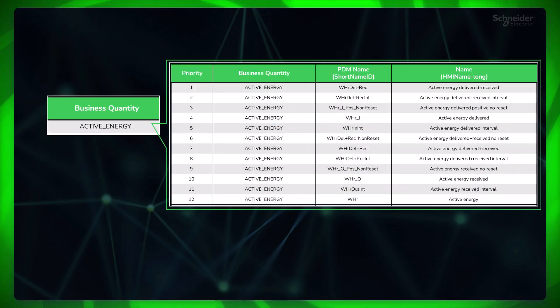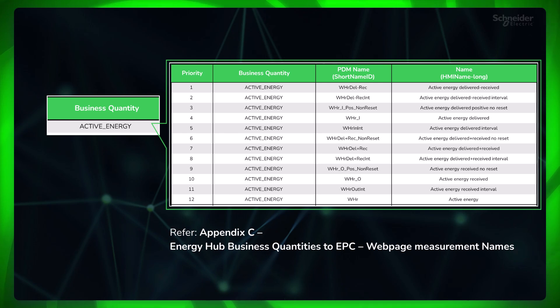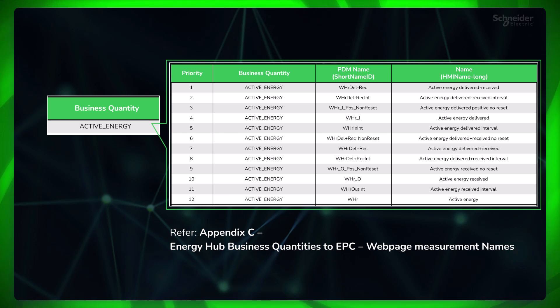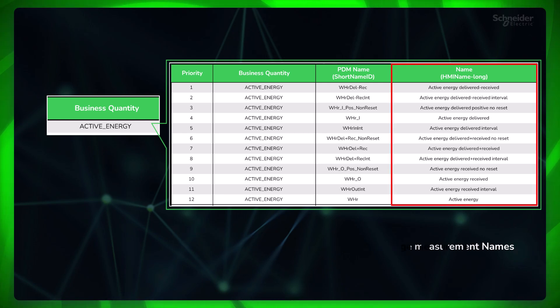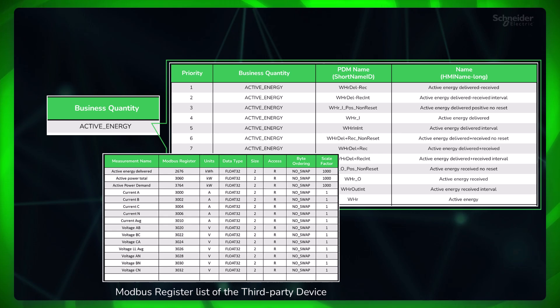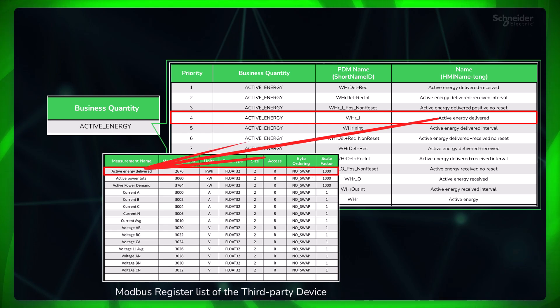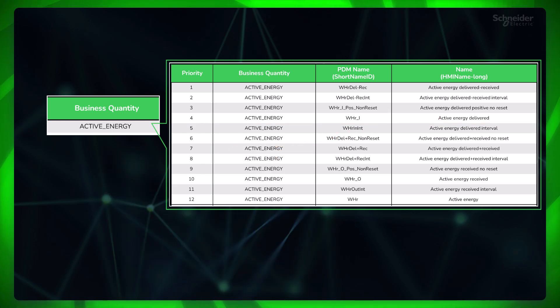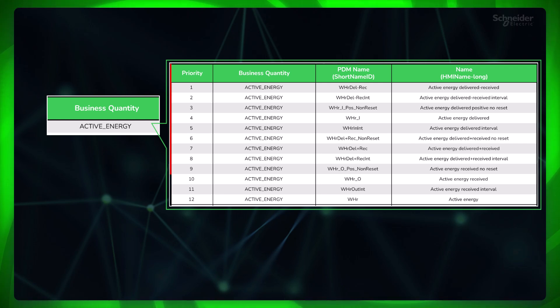Please download the attached document with appendices to refer to later. A business quantity is a group of measurements that have similar functionality. When a business quantity is selected in Energy Hub, it will try to show you the most relevant measurement available for that device as per the product type. For each business quantity, you need to have at least one measurement in the business quantity group mapped in the Panel Server model for it to show in Energy Hub. If multiple measurements for a device are imported, the business quantity will return the measurement higher in priority.